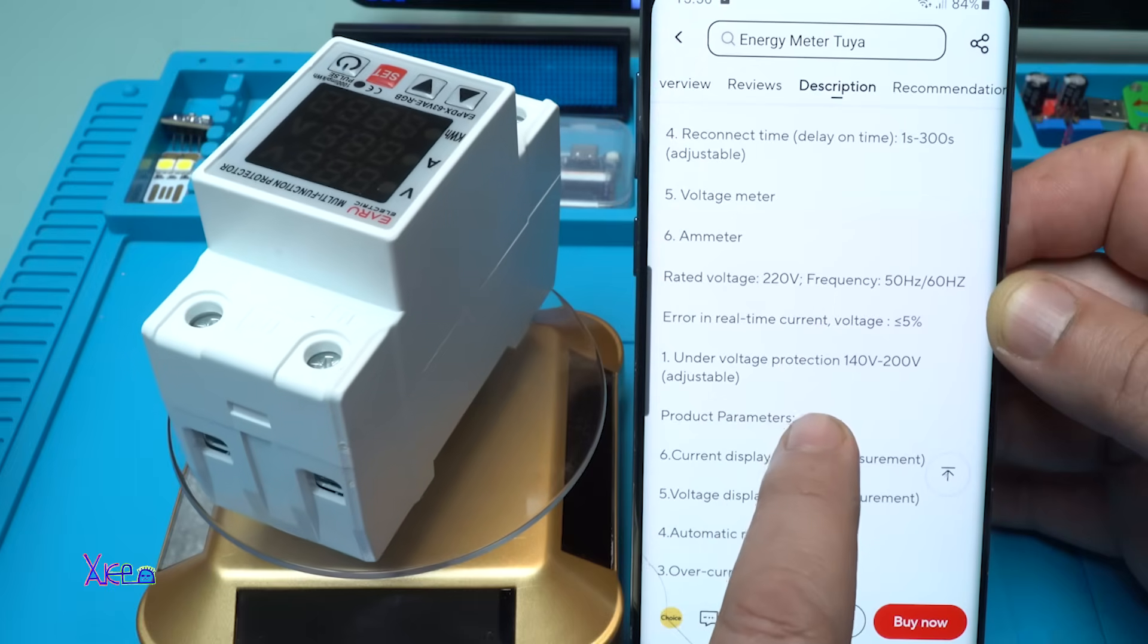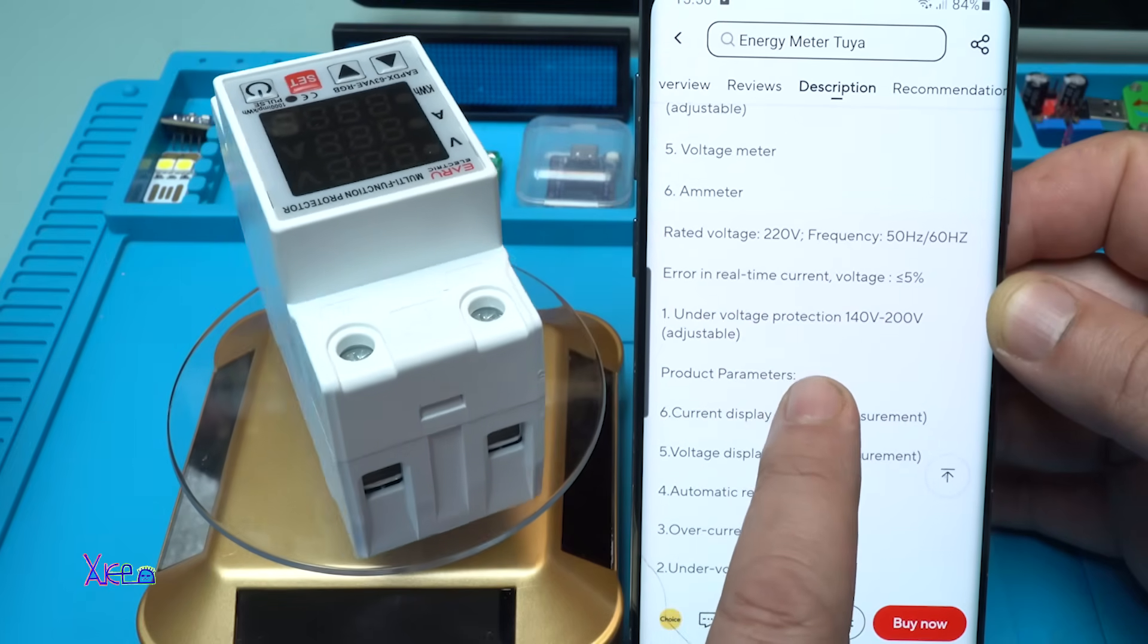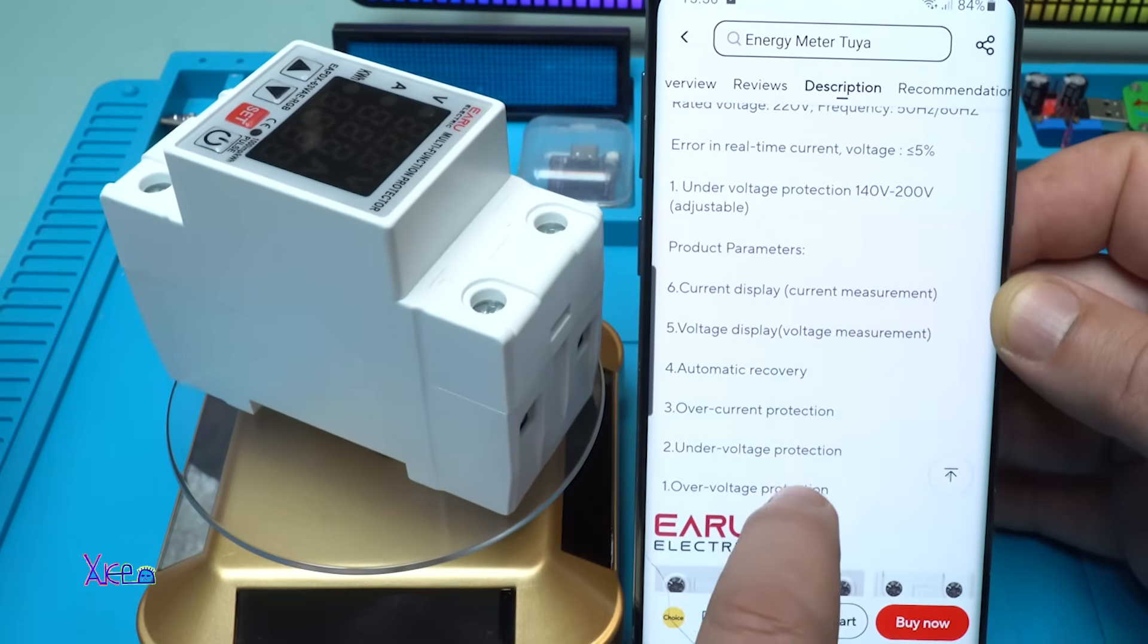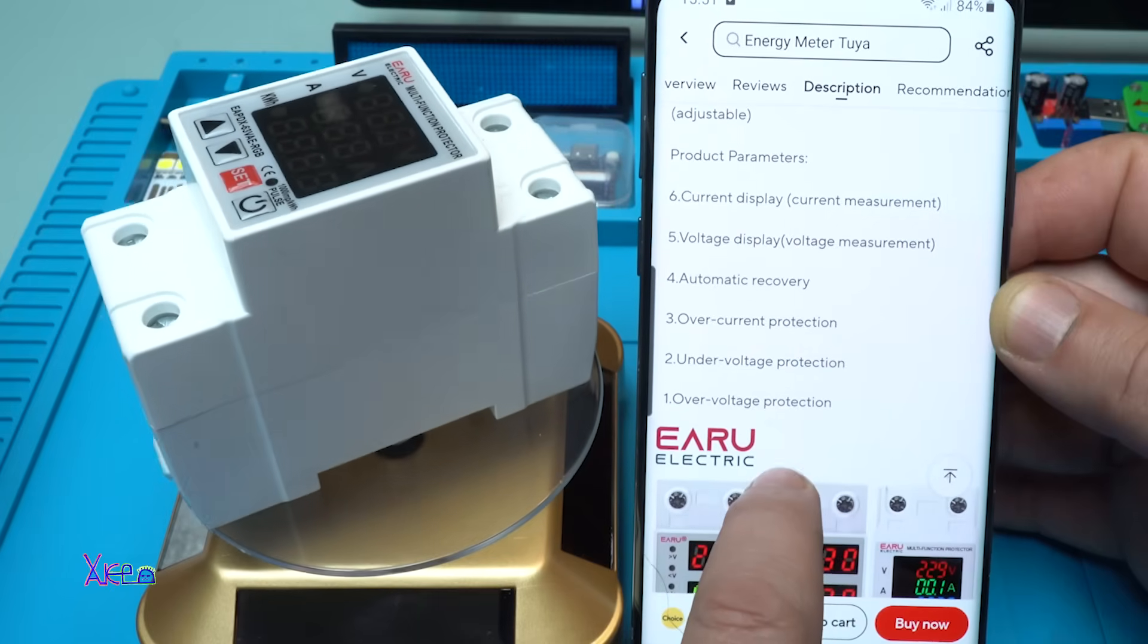Error in real time current voltage 5%. Also we have under voltage protection that can be set from 140 to 200 volts, current display, voltage display, automatic recovery, over current protection, under voltage protection and over voltage protection.